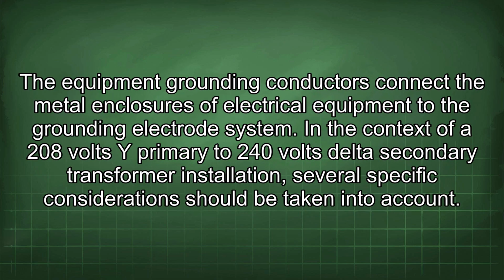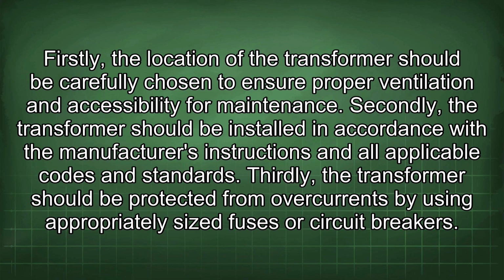The equipment grounding conductors connect the metal enclosures of electrical equipment to the grounding electrode system. In the context of a 208 volts Y primary to 240 volts delta secondary transformer installation, several specific considerations should be taken into account. Firstly, the location of the transformer should be carefully chosen to ensure proper ventilation and accessibility for maintenance. Secondly, the transformer should be installed in accordance with the manufacturer's instructions and all applicable codes and standards.